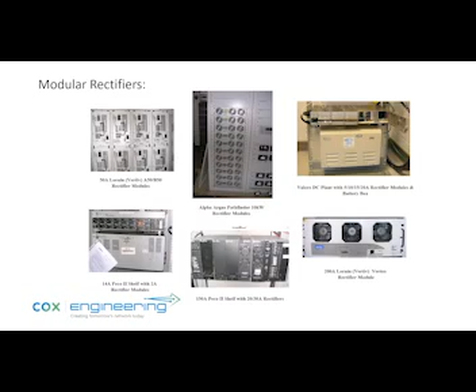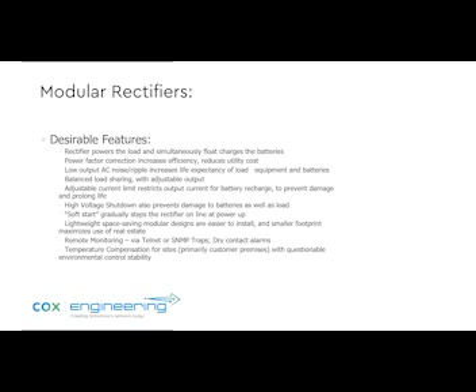So some of the desirable features for modular rectifiers: you can remotely monitor them. They have temperature compensation, high voltage shutdown, and adjustable current limit. So the rectifiers are pretty smart these days. The controllers are able to do an awful lot. They can manage the plant. If you have green considerations, they can cycle through the number of rectifiers that you have so that they're not all on at the same time. Only the number that are needed are on, the rest are in standby, and then you cycle through them to make sure that they all get a little bit of use. Well, that's all possible these days.